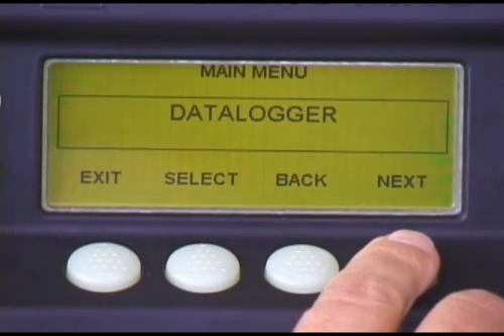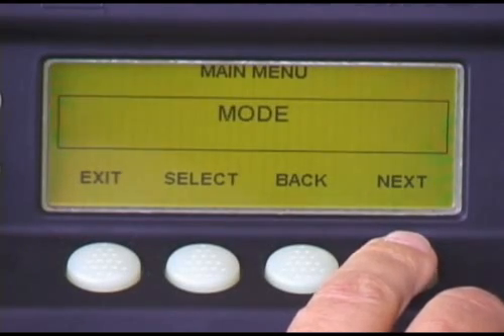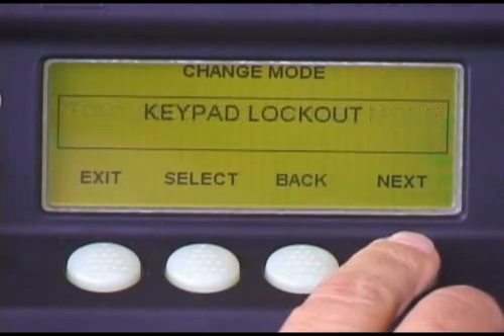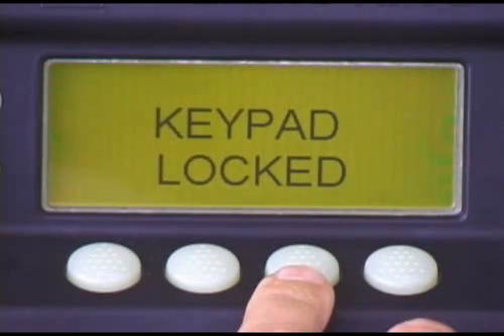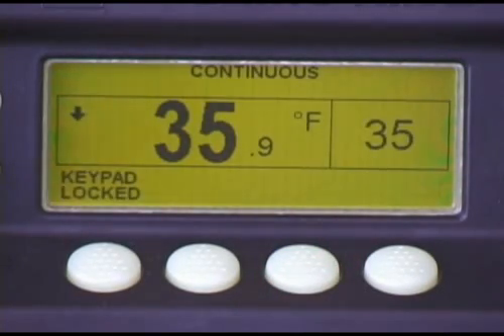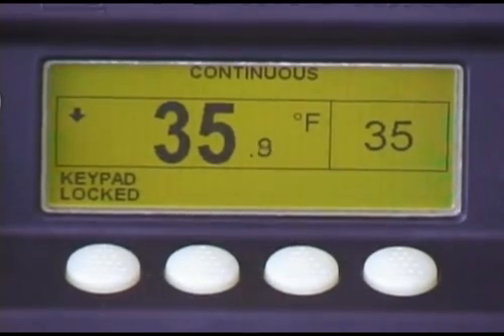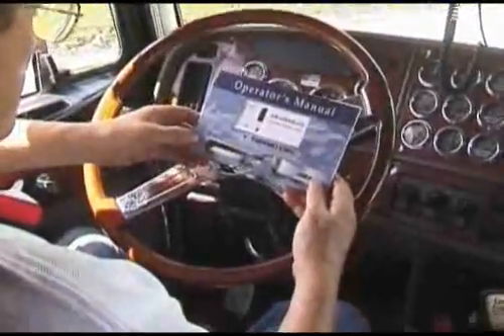For security, and to prevent unauthorized unit tampering, the SR2 keypad can be locked. To do so, press the Menu key. Press Next repeatedly to scroll to the Mode screen. Then press Select. Press Next to scroll to the Keypad Lockout screen. Then press Select. Press Yes to lock the keypad. The standard display will return, and Keypad Locked will appear in the display. To unlock the keypad, press and hold one of the soft keys for 5 seconds or more.